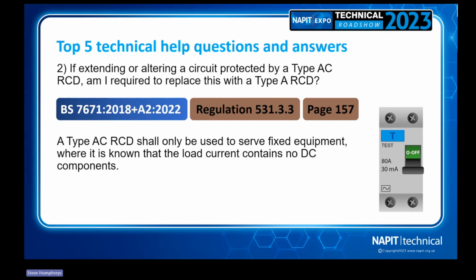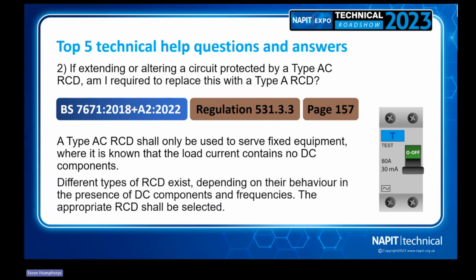Now, the other thing to add at the bottom of that question is the member said a type A RCD. That's not strictly true. If you do have to replace it, the device will depend on the equipment and maybe manufacturer's instructions. The note for that one says different types of RCDs exist, depending on their behaviour in the presence of DC components and frequencies, and the appropriate RCD shall be selected. I remember a while back, someone said to us that for EV charging equipment, for instance, it's always got to be a Type B.